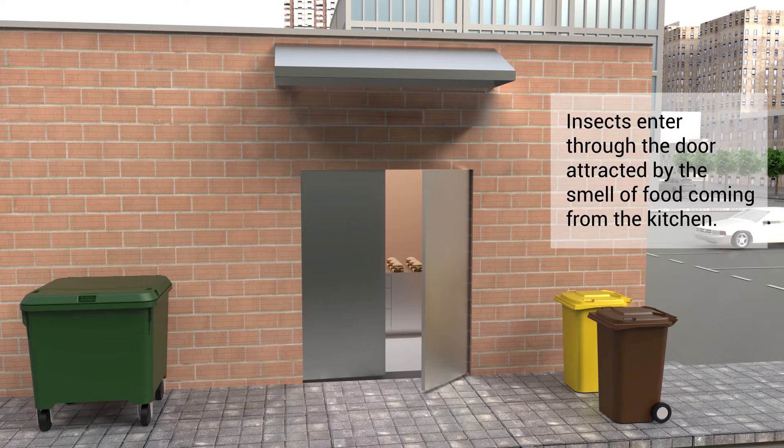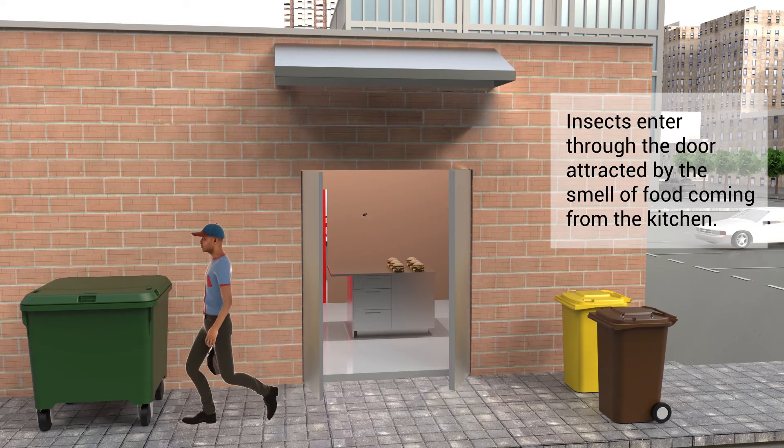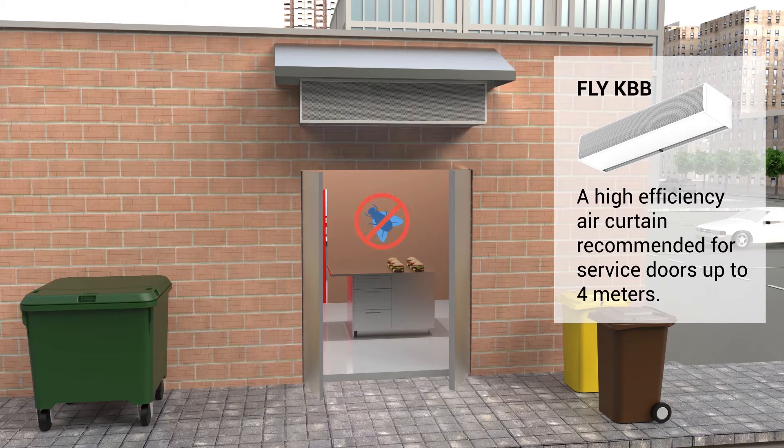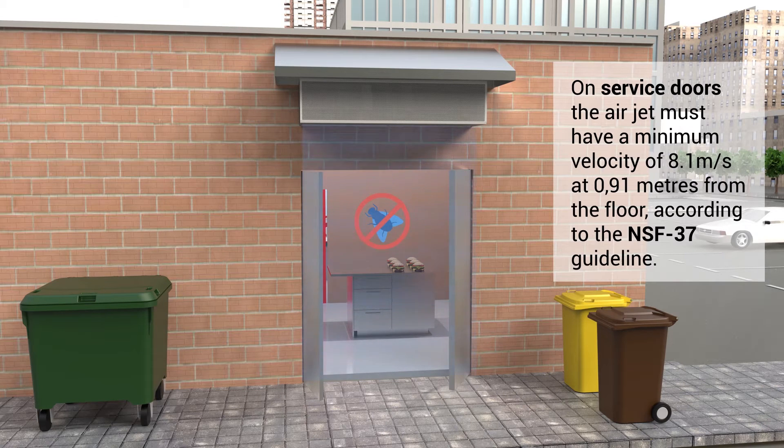Insects enter through the door attracted by the smell of food coming from the kitchen. Fly KBB is a high efficiency air curtain recommended for service doors up to 4 metres. On service doors, the air jet must have a minimum velocity of 8.1 metres per second at 0.91 metres from the floor, according to the NSF 37 guideline.